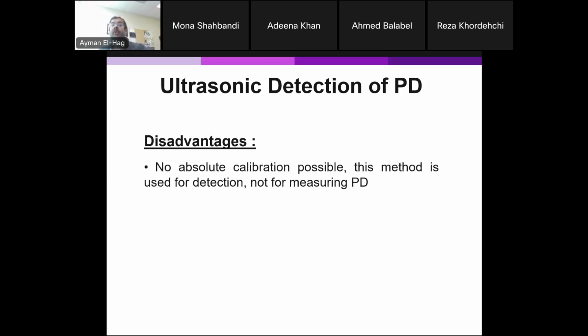Disadvantages: again, there is no calibration. You are measuring a signal, but you don't know the source. What is the actual partial discharge? Why is that? Because imagine you have the same source of partial discharge and you measure at slightly different distances. You measure it at one time at X and then at Y, and you will have two different signals. So distance will impact the magnitude that you measure. Also, it depends on the medium between you and the sensor. It depends on the location of the partial discharge: is it inside the insulation or outside the insulation? So it is good to detect that there is partial discharge, but you cannot really calibrate it and say it's a high level or a low level.